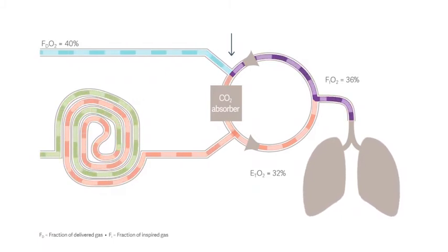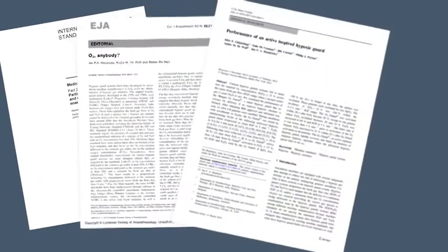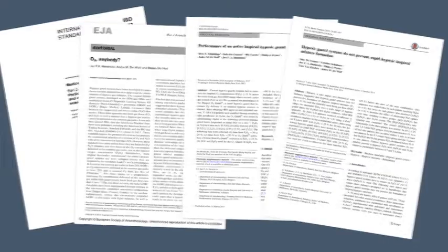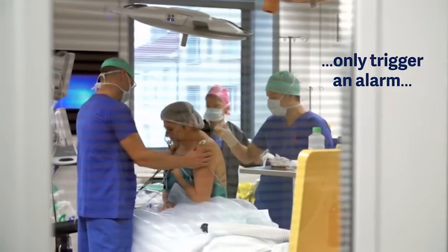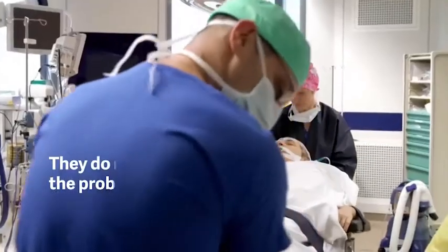type of anesthesia device. Safety standards require anesthesia systems to be equipped with a protection solution to prevent hypoxic mixtures. But conventional protection solutions will only trigger an alarm if the inspired oxygen level becomes too low. They do not correct the problem. But we have a solution.